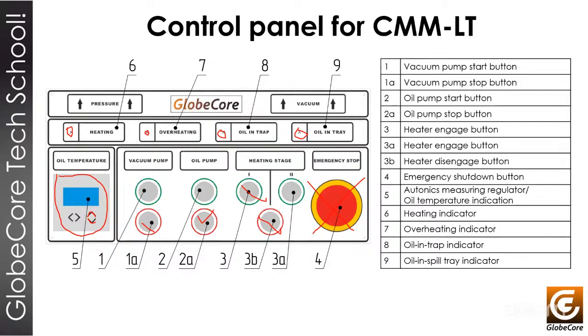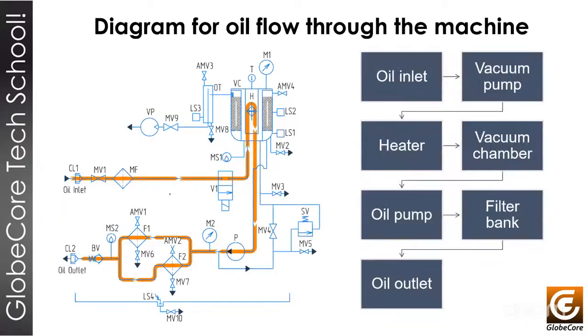Well, we will have the flow of the oil inside the machine, which I presented before and is really easy. In summary, you will have the oil inlet of the machine here. Then you will have the vacuum generated by this pump that makes the oil come into the machine. The oil will go to the heater. Okay, the oil will go here, then pass to the vacuum chamber, and then the oil will go to the oil pump, then pass through the filters, and then go out of the machine.